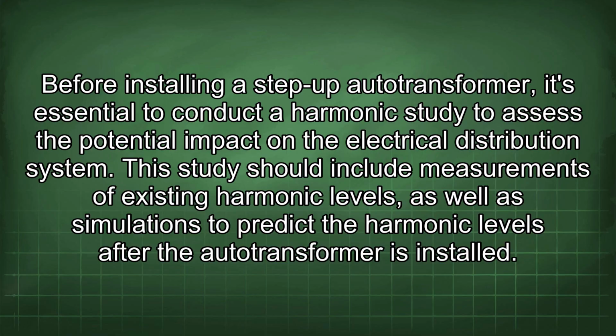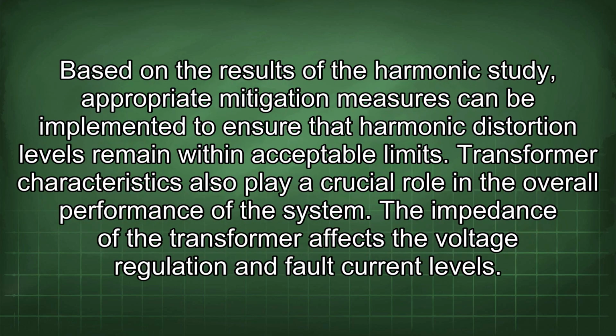This study should include measurements of existing harmonic levels, as well as simulations to predict the harmonic levels after the autotransformer is installed. Based on the results of the harmonic study, appropriate mitigation measures can be implemented to ensure that harmonic distortion levels remain within acceptable limits.